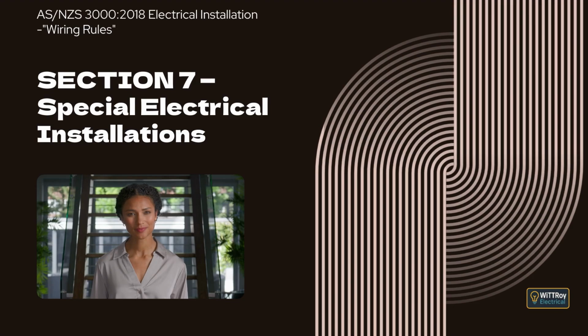Clause 7.3.8.3 Standalone power systems. This clause introduces requirements for standalone systems that are not connected to the electricity network. Clause 7.3.8.3.1 General. This clause explains that the consumer mains of the electrical installation must be connected to the output of the electricity generating system. Clause 7.3.8.3.2 Switching. This clause explains that control of the electrical installation supplied by a standalone system must be arranged in accordance with Clause 2.3. Clause 7.3.8.3.3 Connection. This clause explains that the method of connection for a standalone system must comply with the AS/NZS 4509 series, and that typical arrangements include a local MEN connection at the switchboard.